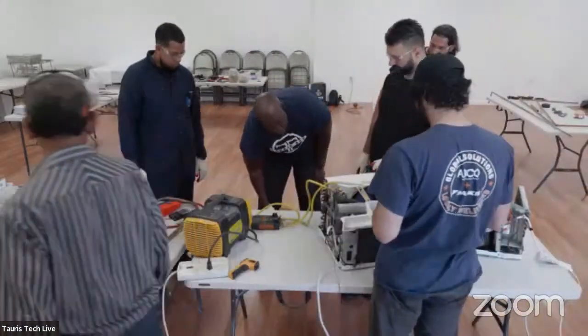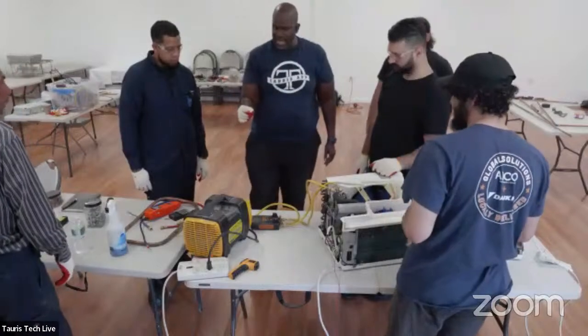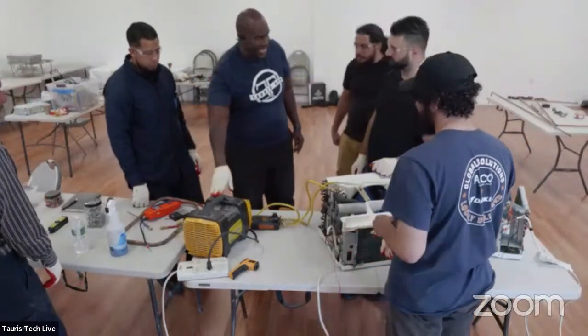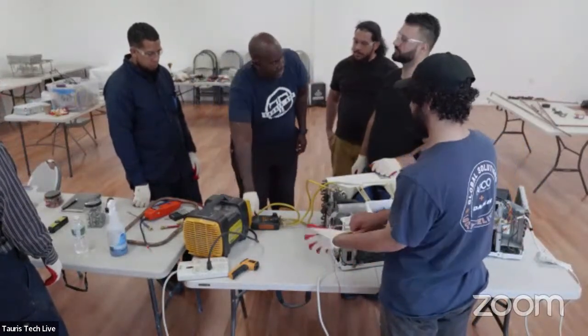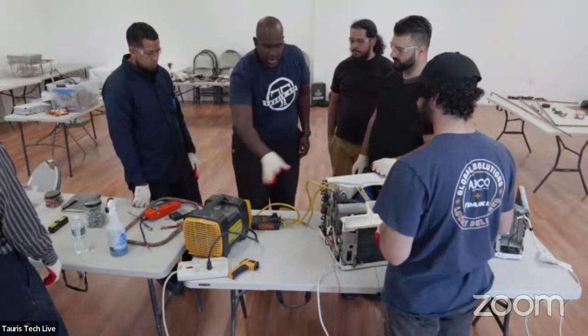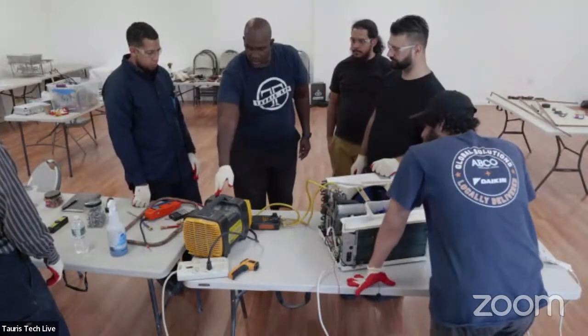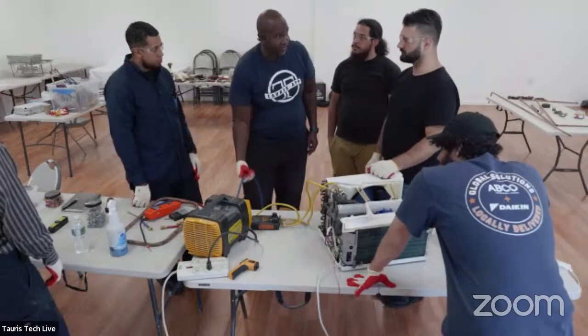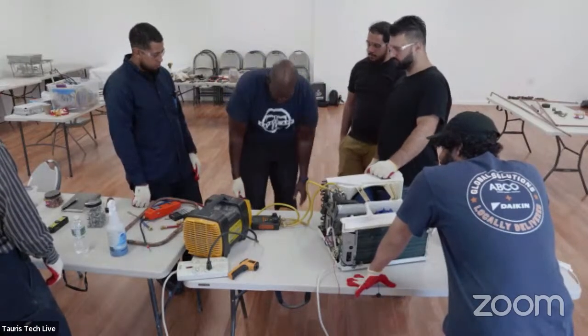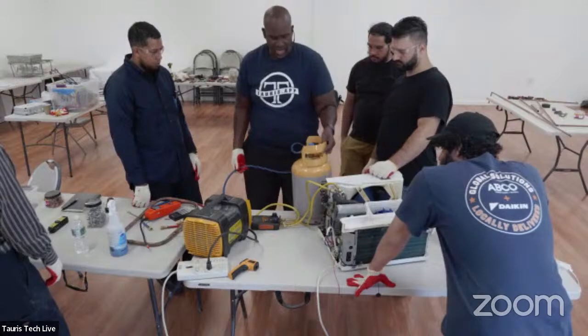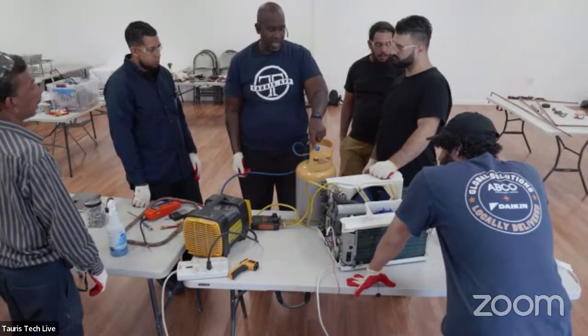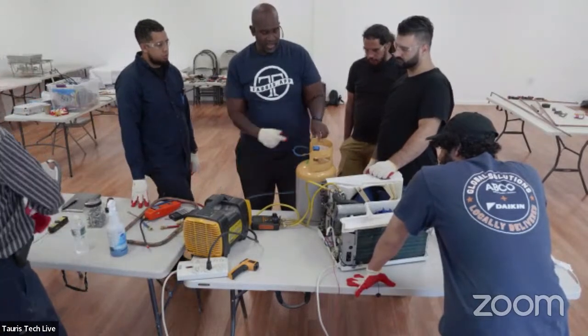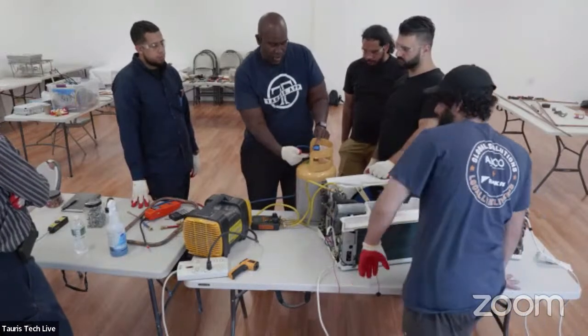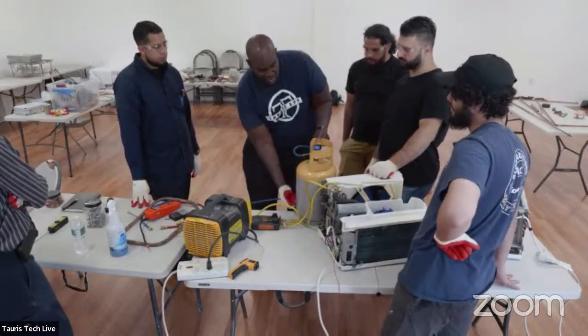So what you have to understand is this has a condenser. That's why you have these vents here. There's a condenser coil - the compressor sucks the refrigerant out, but then it condenses it, so this is filled with liquid. The reason I put it on this side is the gas side - it's the liquid side, it's the gas side - because there's a dip tube here. If I put it on this side, the pressure is going to push even more liquid in it.